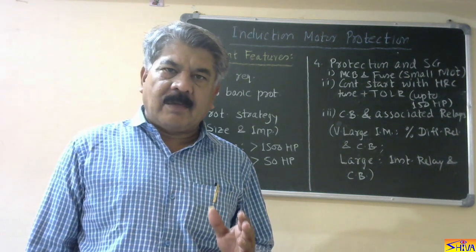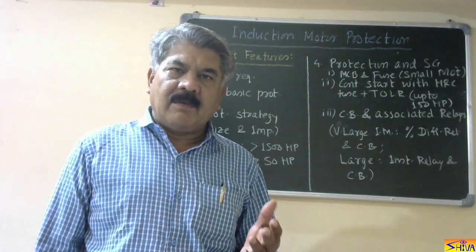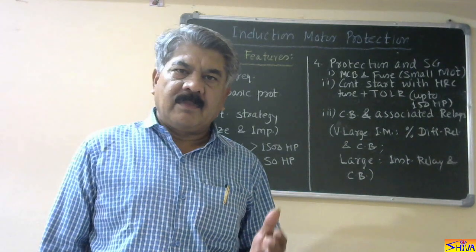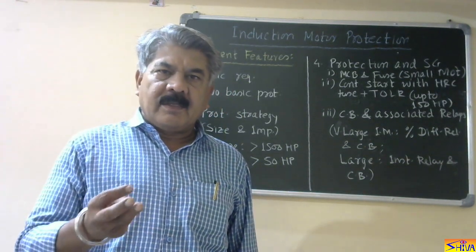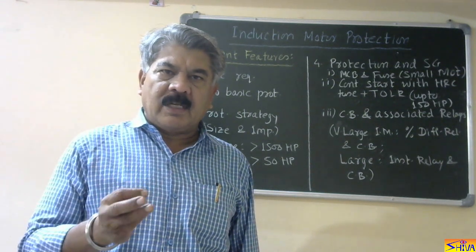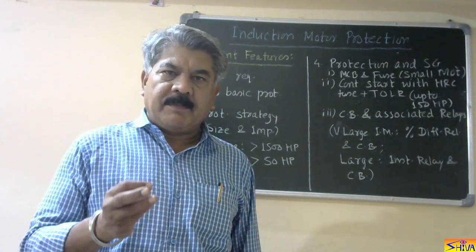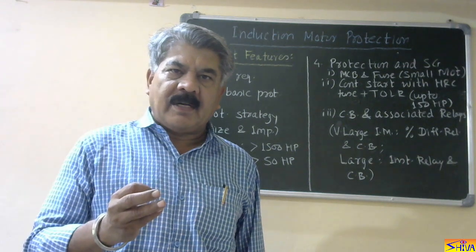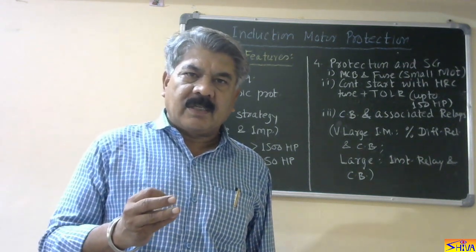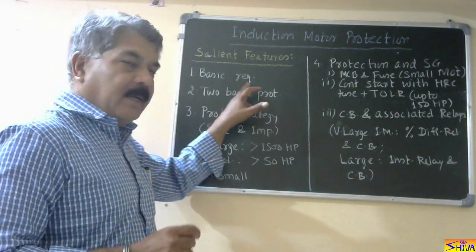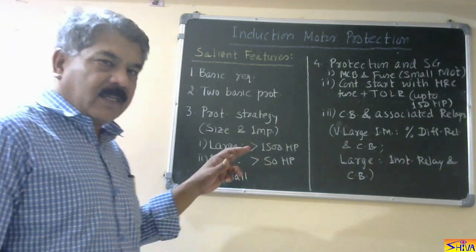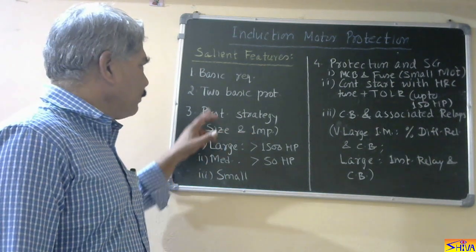And third requirement is, obviously, whenever there is fault, there is short circuit, then the protection should operate. So first, it should not operate during starting. Second, it must allow the motor to take overload for permissible time. And third, it must operate when there is short circuit or fault. So that is the basic requirement of all the protections of the induction motors.